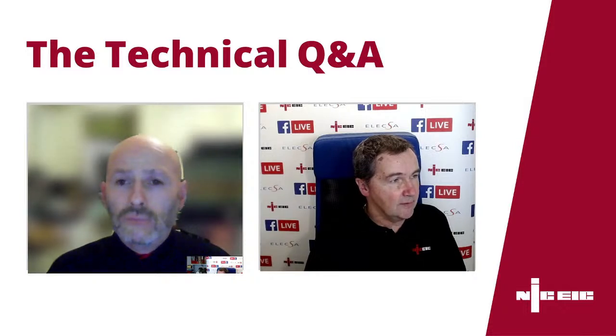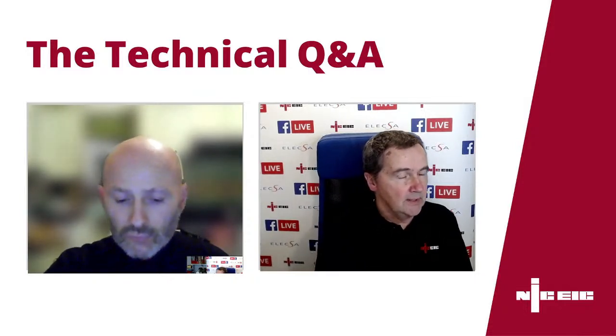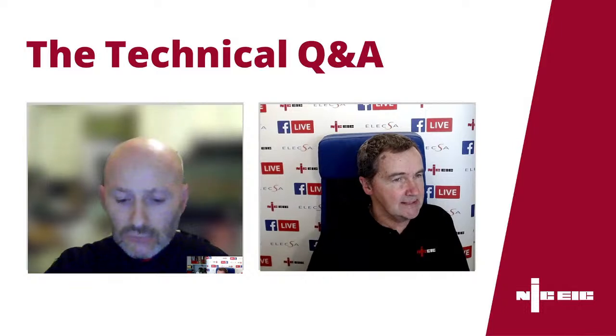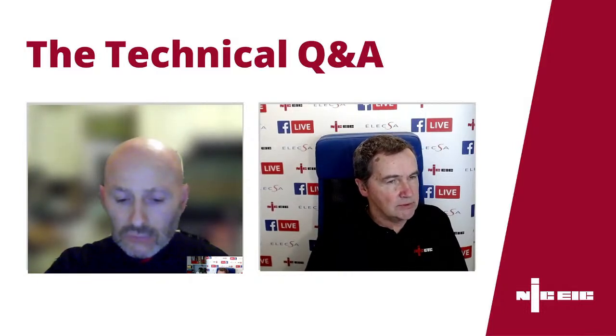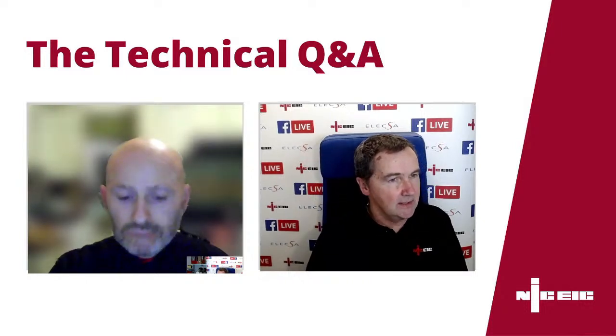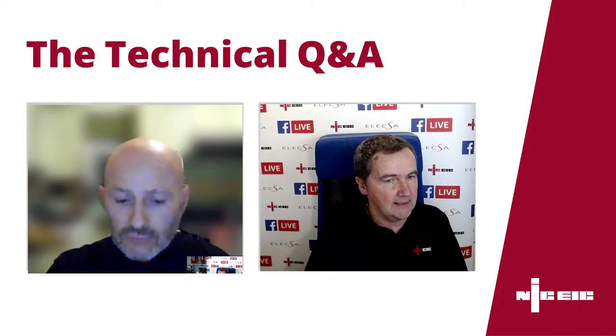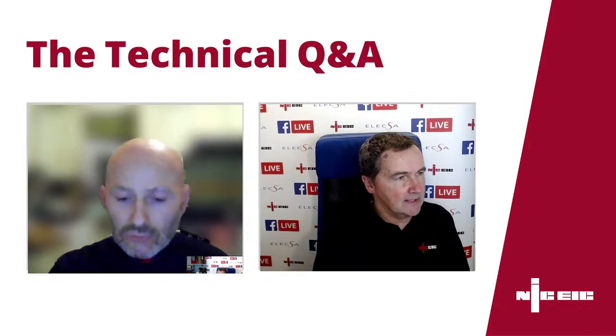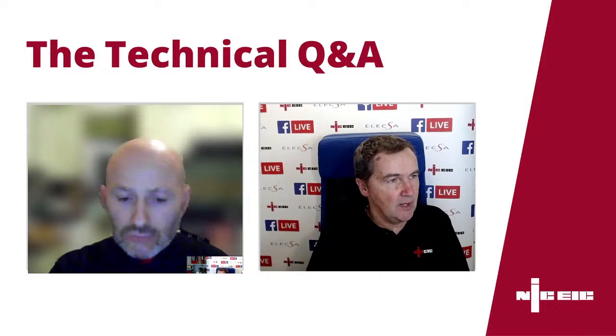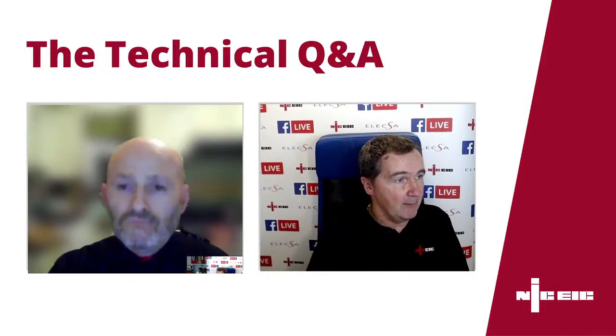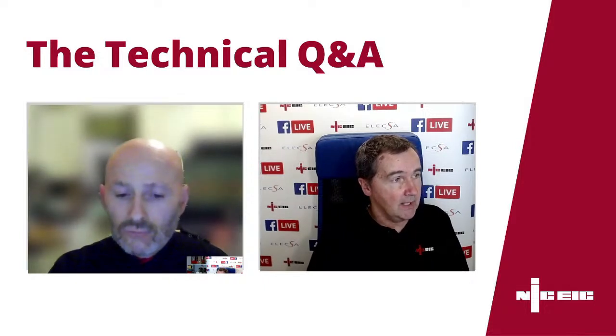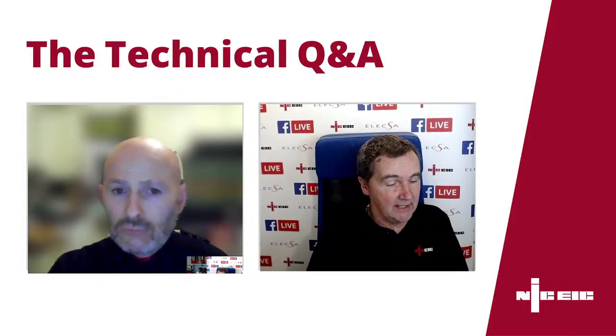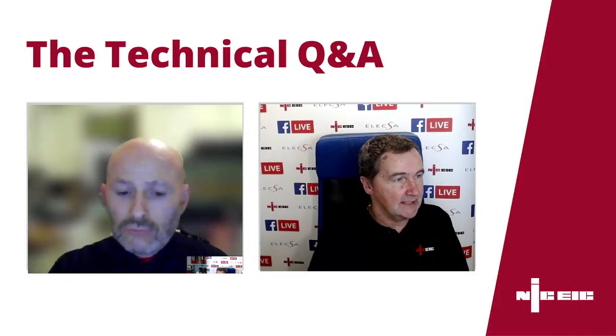On the basis of extending, I think we would recommend against it, because I was always brought up along the lines of every potential connection is a weakness and a potential point of failure. So we would always suggest that your bonding conductors to the extraneous conductive parts should be continuous. Perhaps a through crimp would be a better solution than an adaptable box with connector blocks in, because it would be seen as more durable.